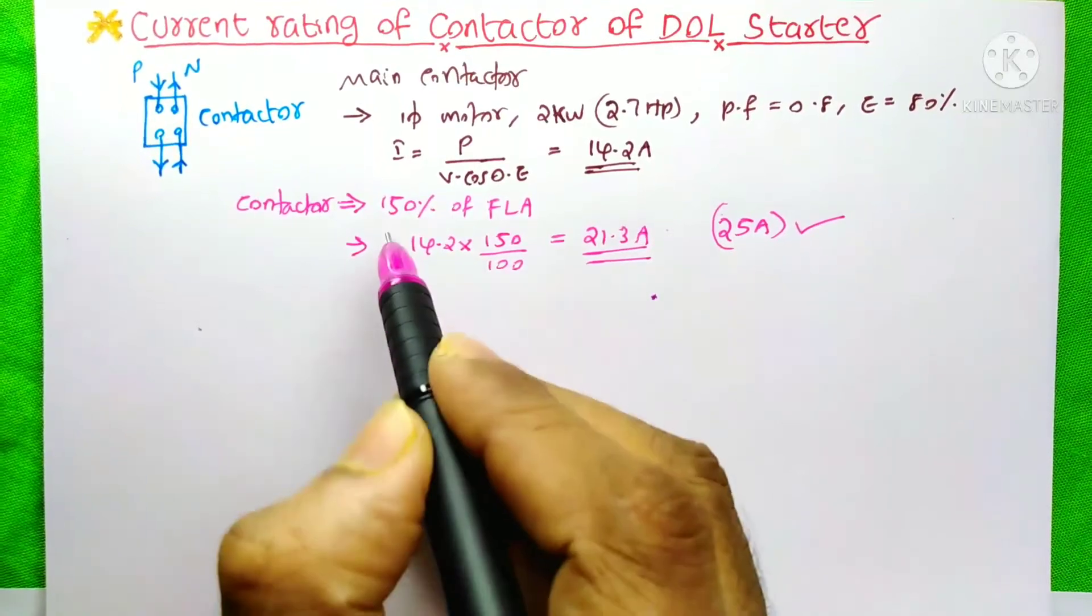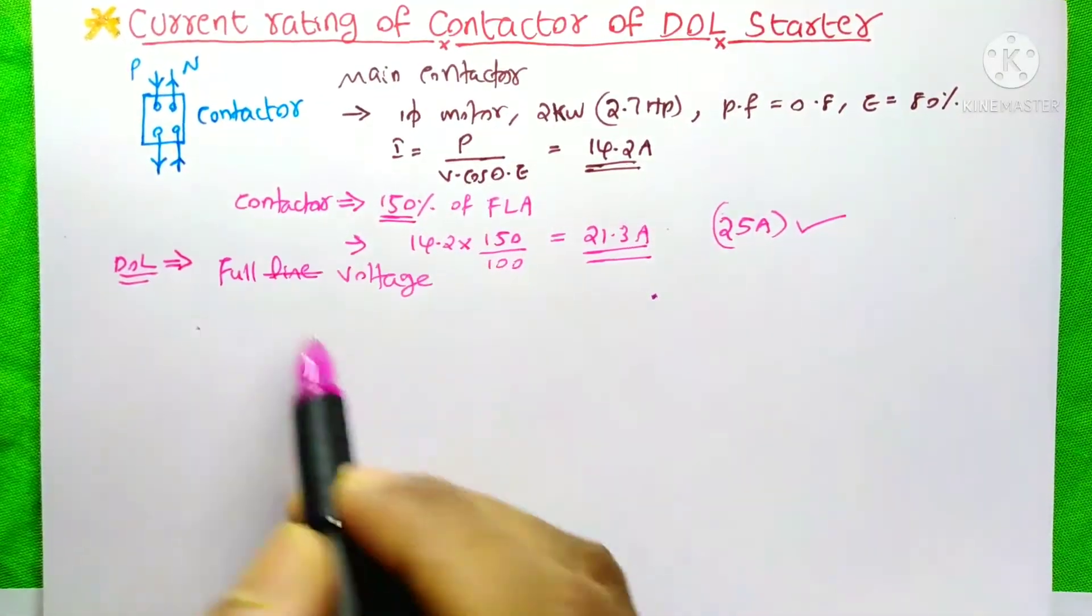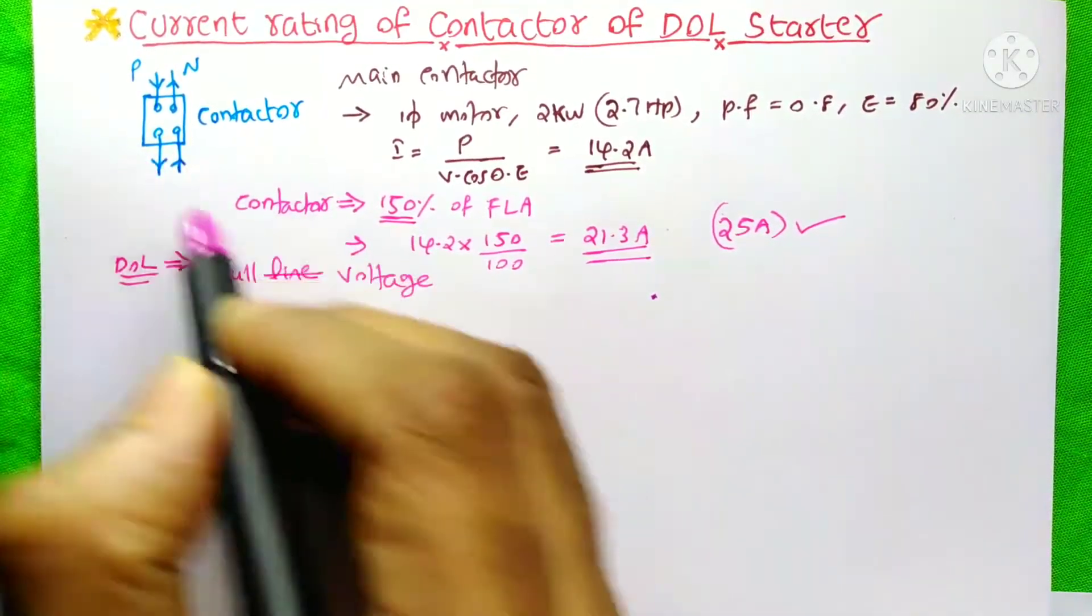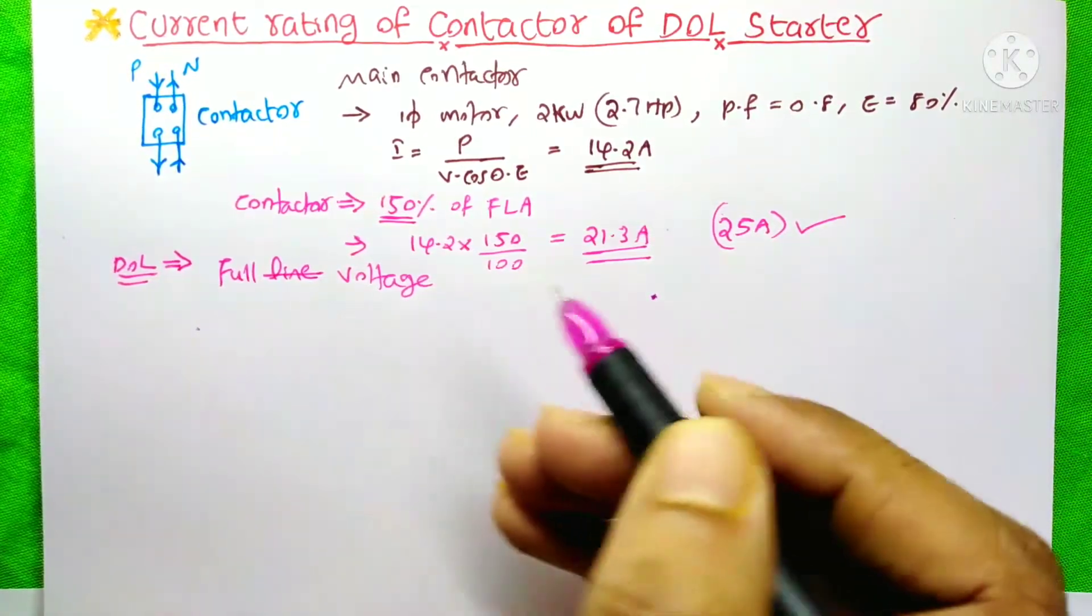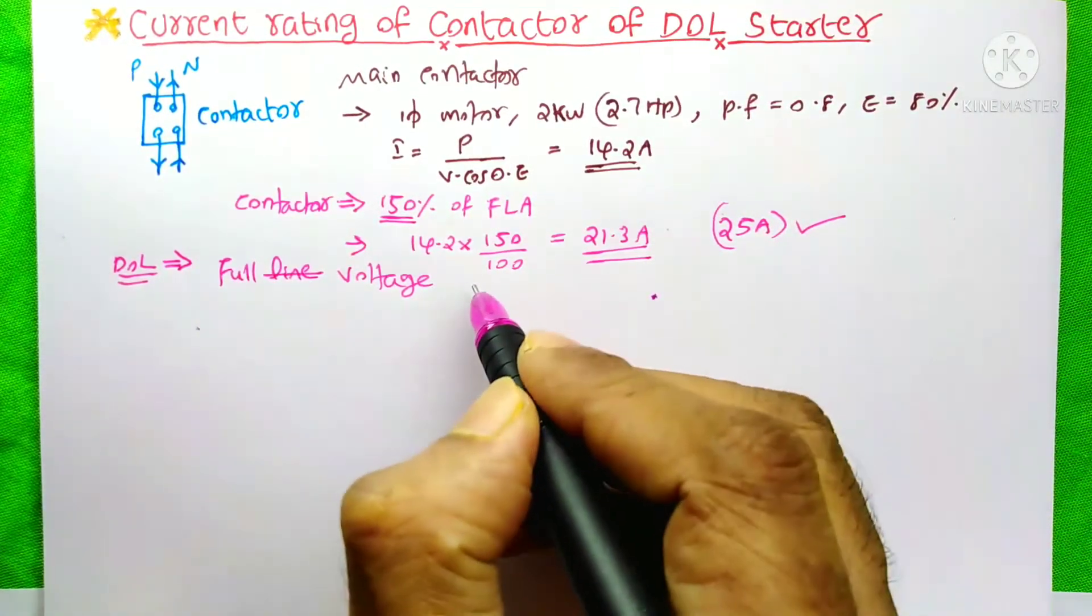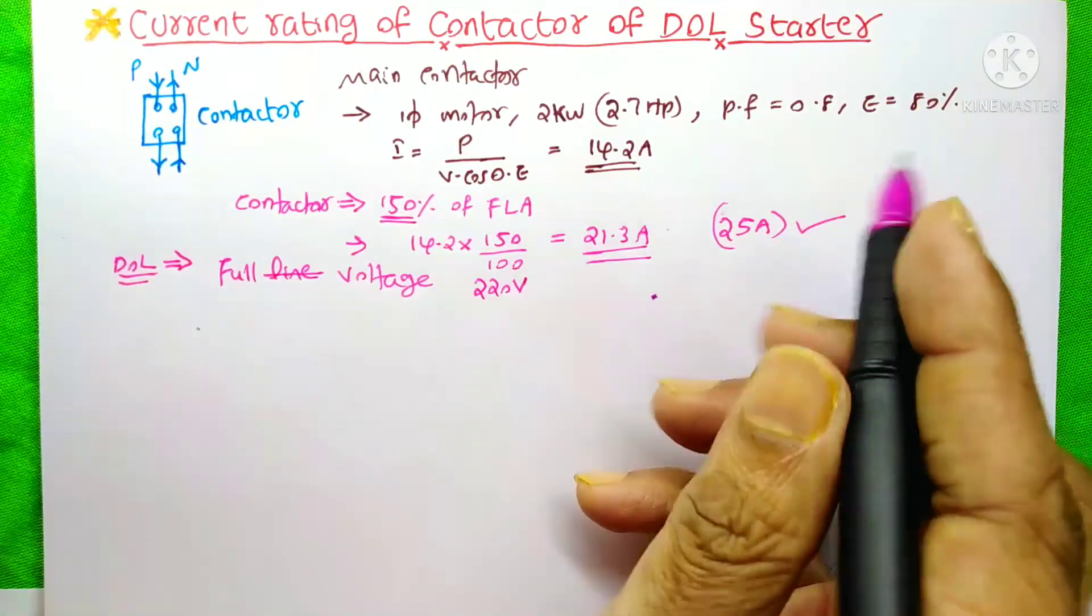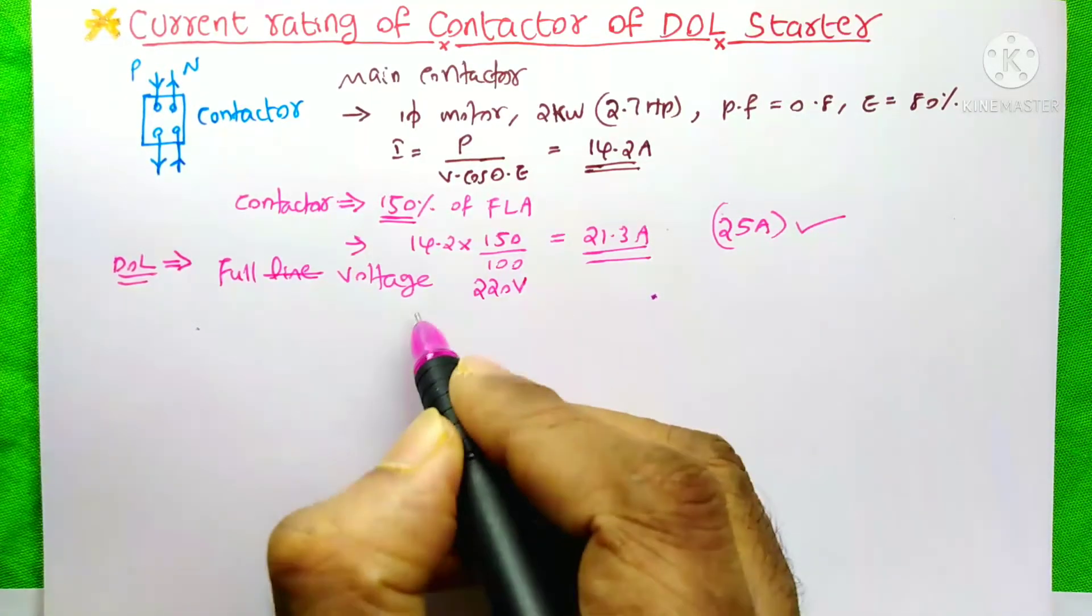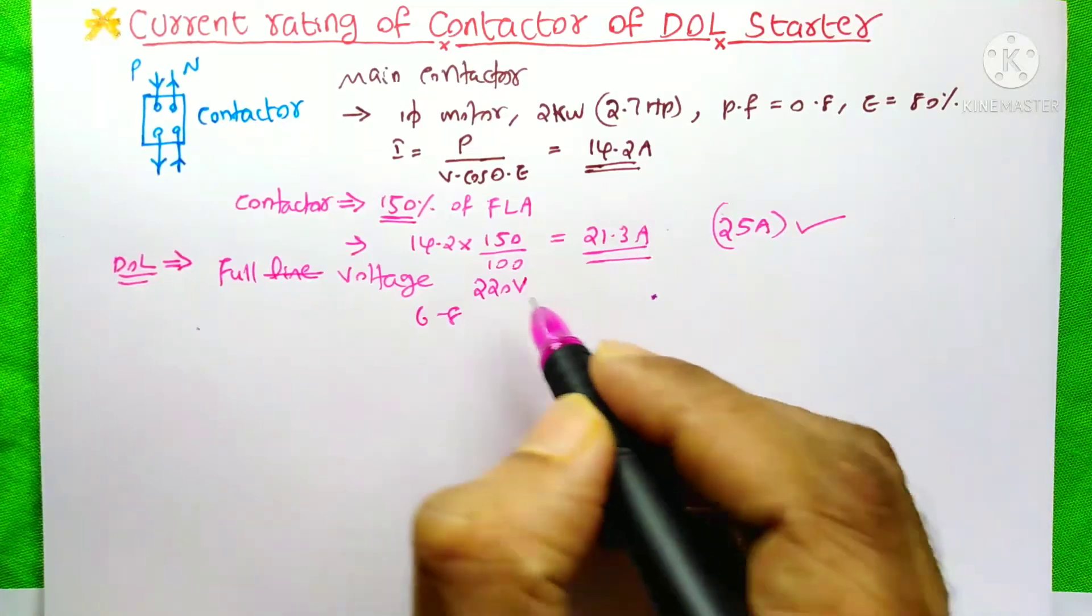Here you might be thinking, why do we consider this 150% of the full load ampere? On the starting time, we apply the full voltage to the phases of the motor. That means there is no reduction of the voltage. So in this case, 220 voltage will be applied directly to the motor's windings. At this time, you know the motor will take 6 to 8 times its rated current, only for a few seconds.